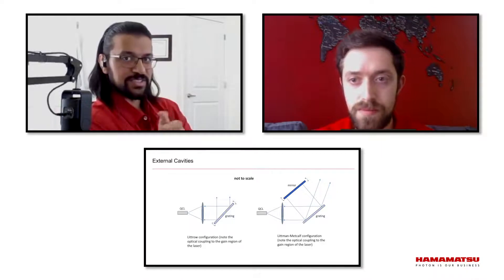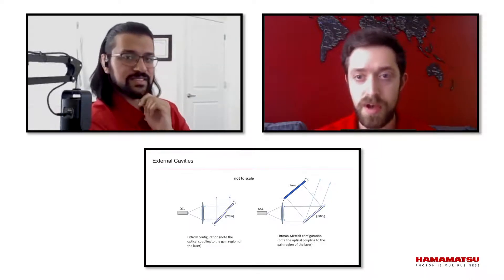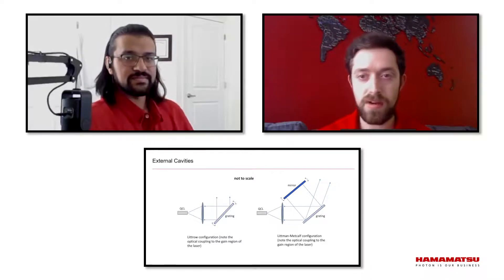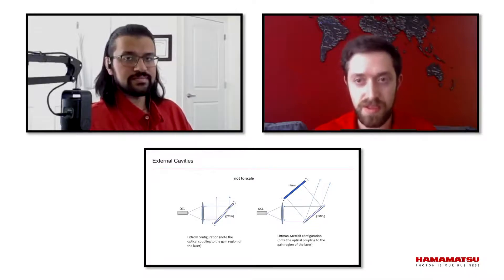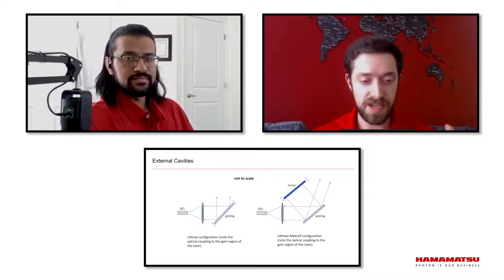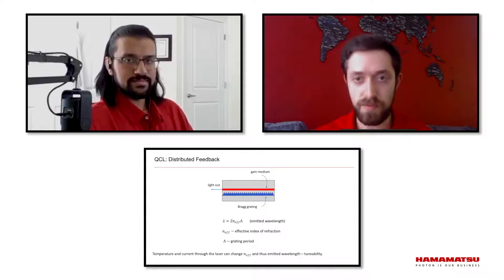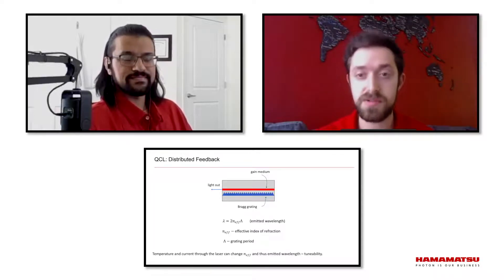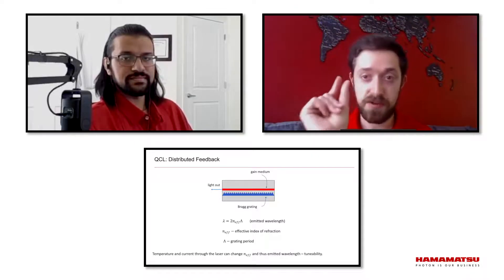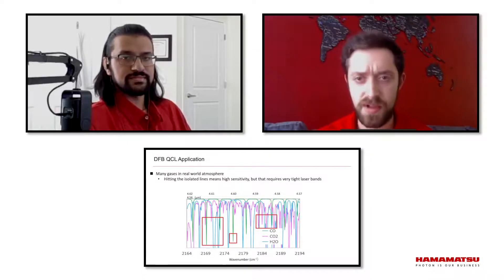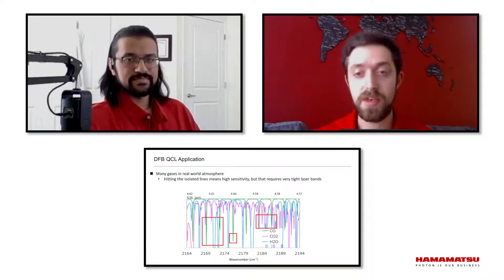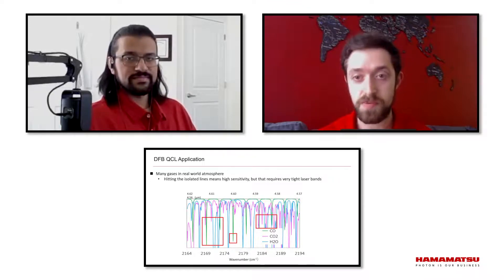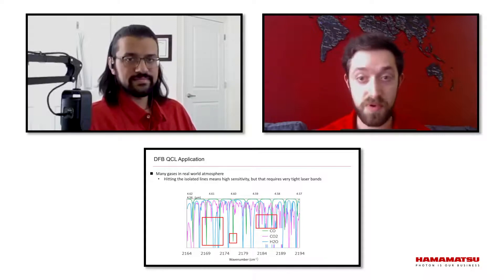What other types of QCLs are there? There are kind of three main areas. First, external cavity QCLs — there are many subtypes, but the important fact is that there is an optical system around the gain chip achieving broadband output. Alternatively, there is the DFB laser — the Distributed Feedback Laser. This uses a grating system that achieves a single frequency at a very tight line width. This is fantastic for gas analysis, namely absorption spectroscopy, and enables extremely high sensitivity gas measurement of parts per trillion, and in academic settings, parts per quadrillion.